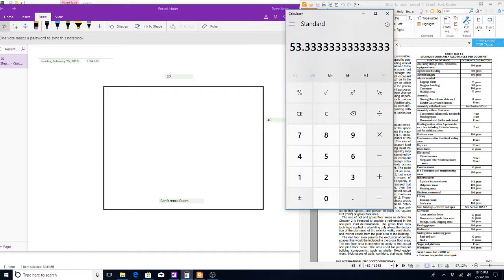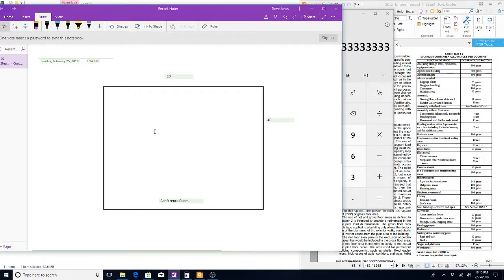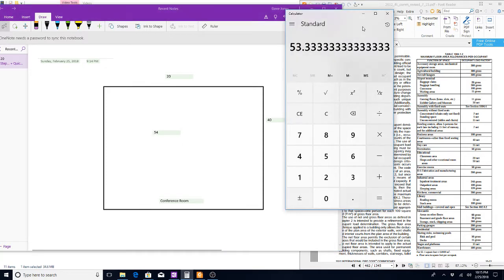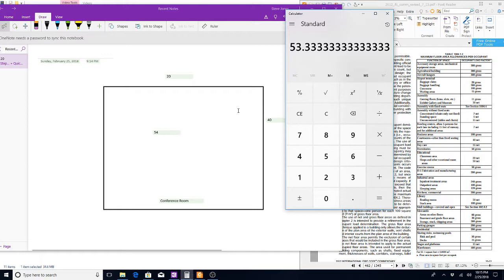That gives us an occupant load of 53.3. The occupant load rounds up to 54, because you can't have a third of a person. So we have figured a conference room with tables and chairs, and the occupant load is 54.